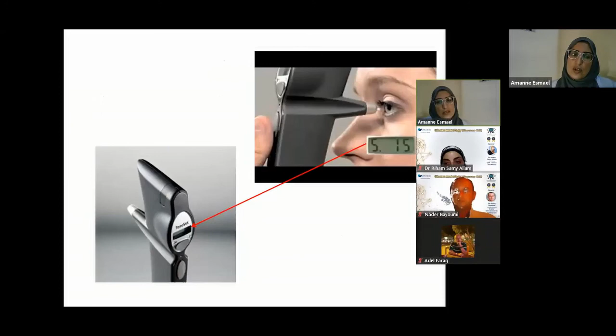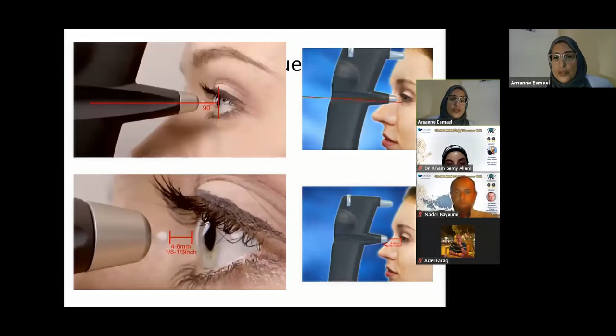How do we take measurements? The advantage of this device is that it doesn't require topical anesthesia. However, you need to hold your device absolutely at right angles with the cornea. You instruct your patient to look straight ahead, and you need to keep it at a distance between 4 and 8 millimeters. A distance that is further or closer to the cornea will not give you readings, and neither will tilting of the device. So what are the pros and cons of rebound tonometry by iCare?